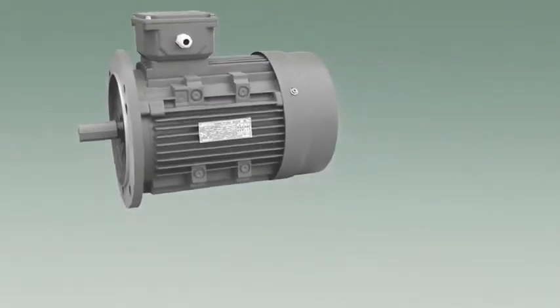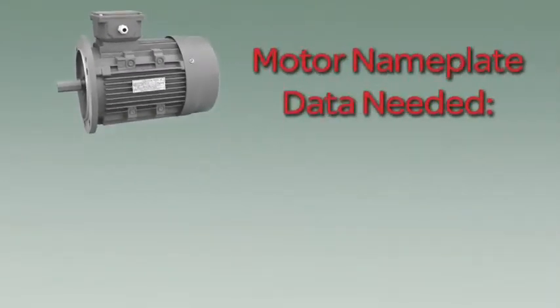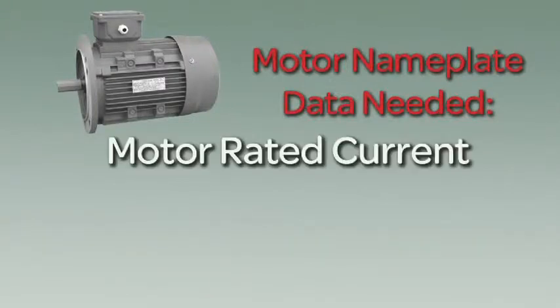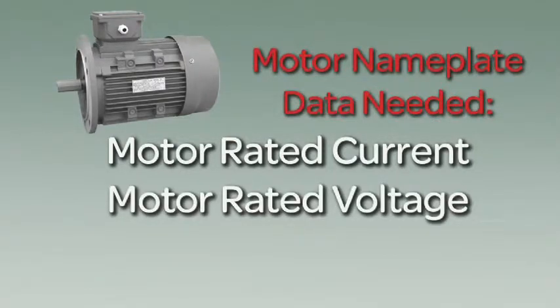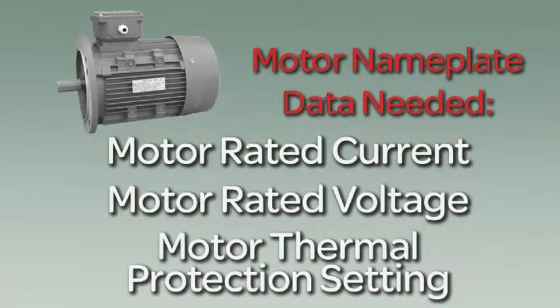Having the following data from the motor nameplate readily available will allow you to configure these parameters in just a few minutes: motor rated current, also called full load amps, motor rated voltage, and motor thermal protection setting. Often this is the same value as the motor rated current.